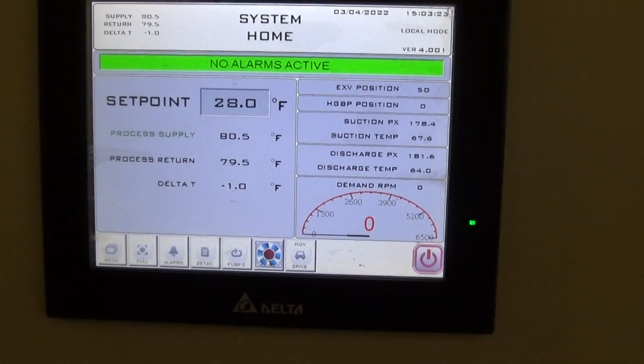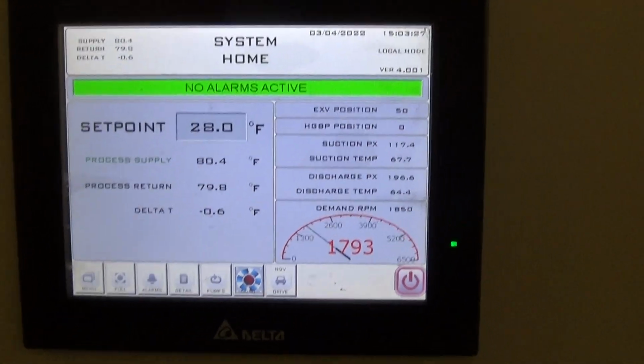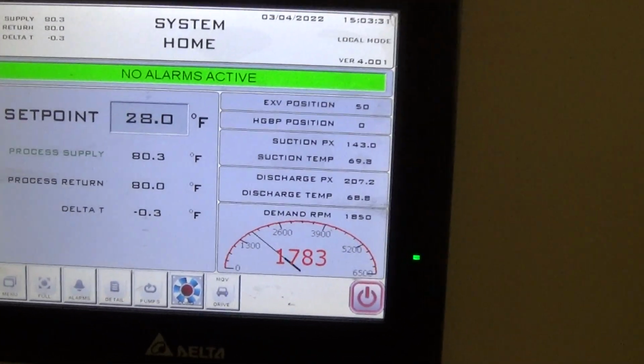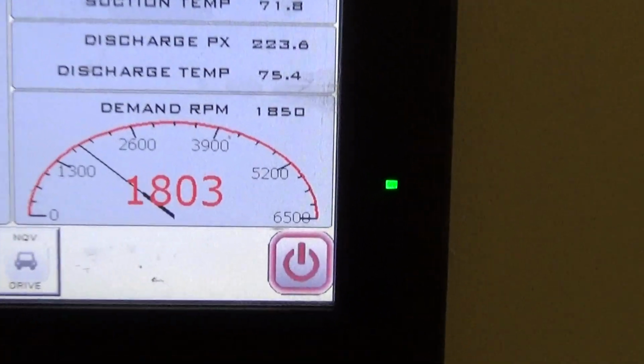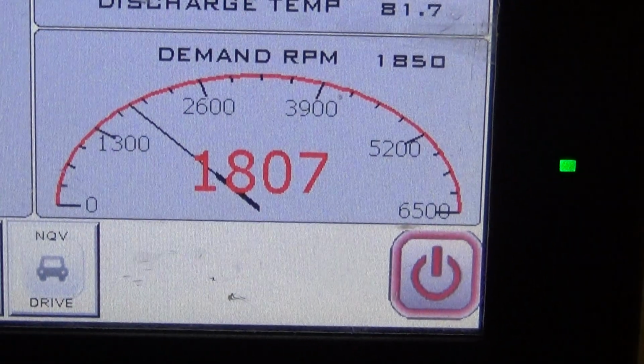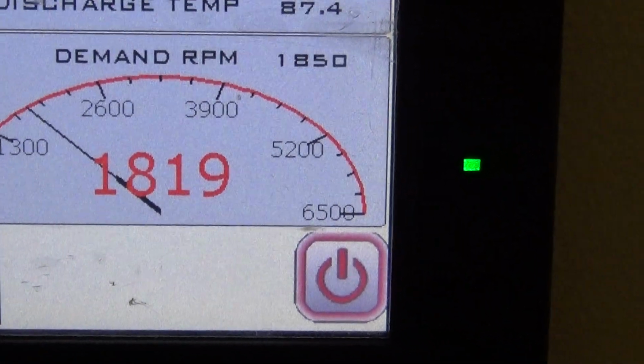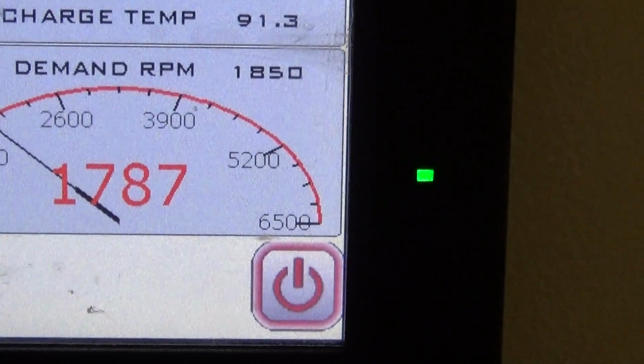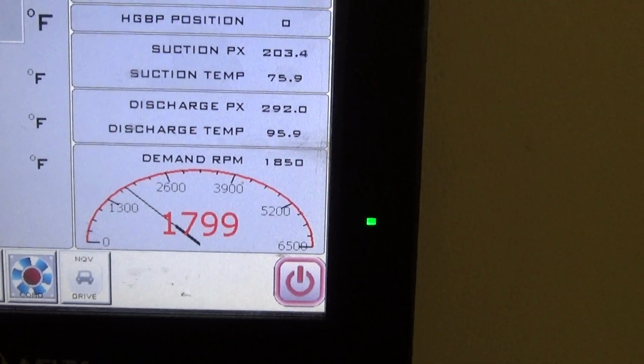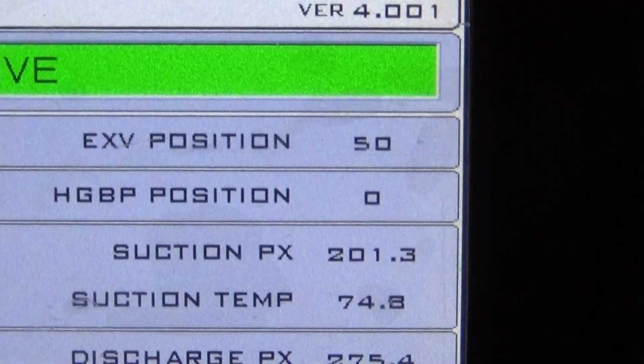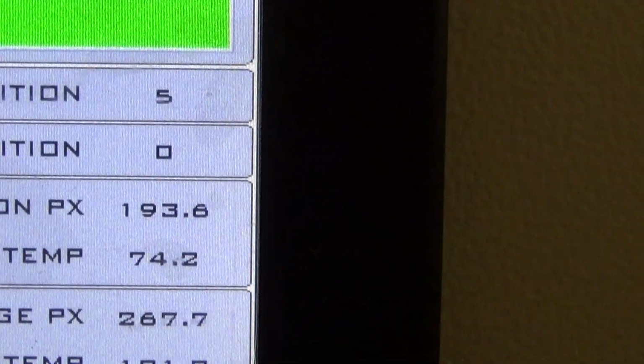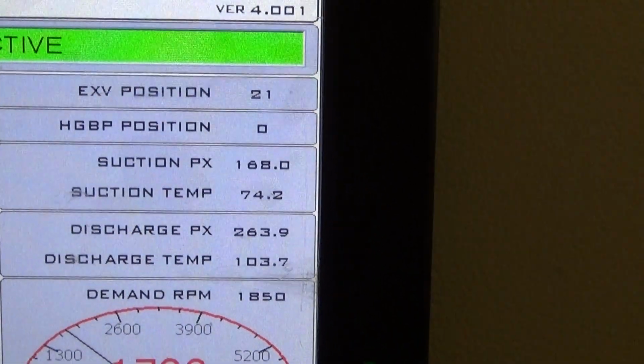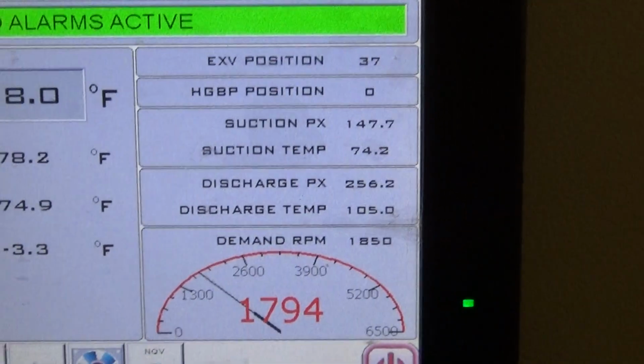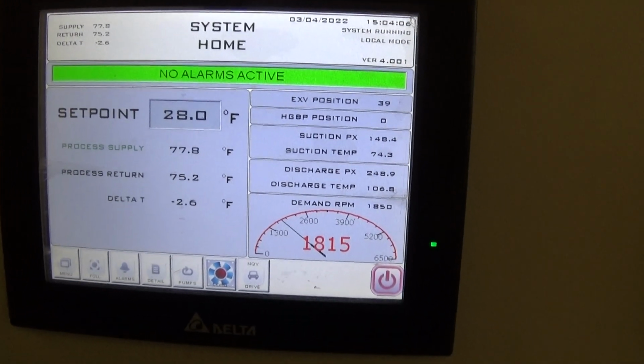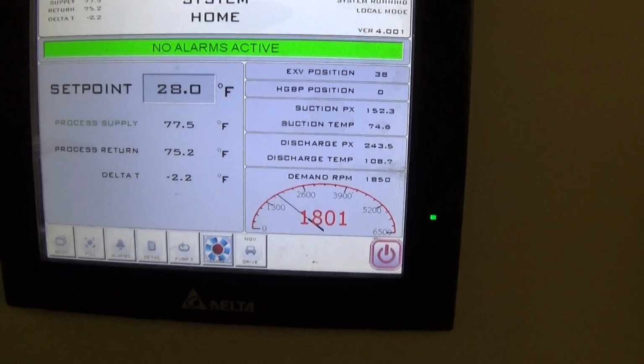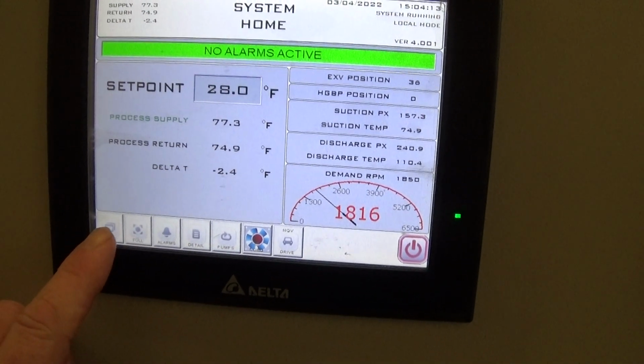And there's going to be some type of delay or so before we hear the compressor turn on. But just a slight one in this case. That very slight noise that you hear, that's the compressor running already, which is amazing. This here is a little tachometer essentially, showing us that the compressor is running about 1800 RPMs, which is not much demand. Some of the items you see here: electronic expansion valve, hot gas bypass, position, suction pressures, suction temperatures. Many of these things you shouldn't have to check, but everything's adjustable. I'm going to go back to menu here.